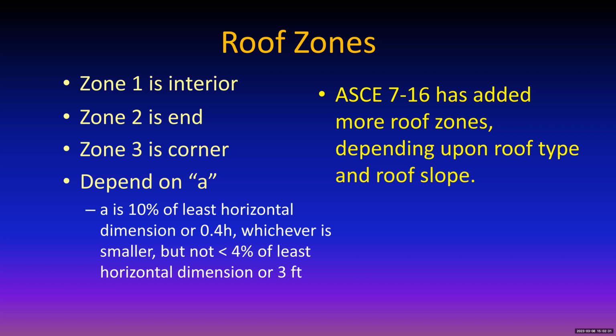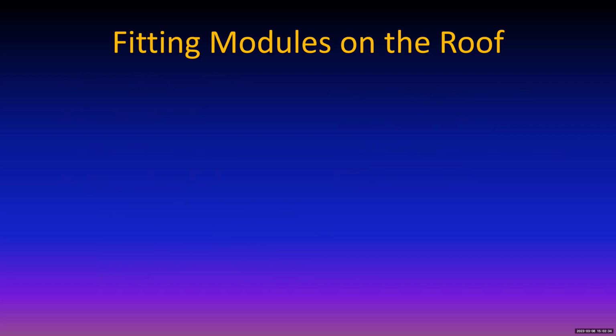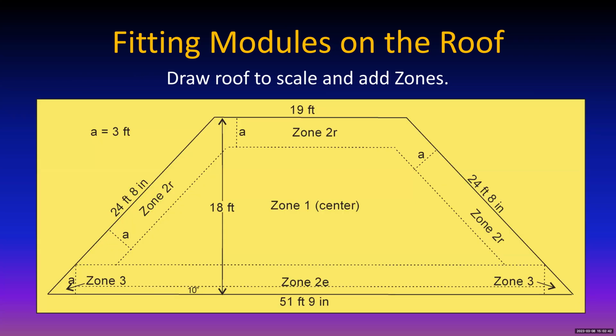Okay, so once you pick the module, then you want to see if it'll fit on the roof. Now, maybe you're going to draw your roof to scale first and add the roof zones, okay? And it might look something like this. And maybe you want to keep the wind resistance at a minimum in zone 1. It turns out you don't really have to do that usually, except in some very special cases. But if you can keep what you need and what you want in zone 1, then you don't have those extra pressures that are generally present in zone 2R and zone 2E in this particular hip roof configuration.